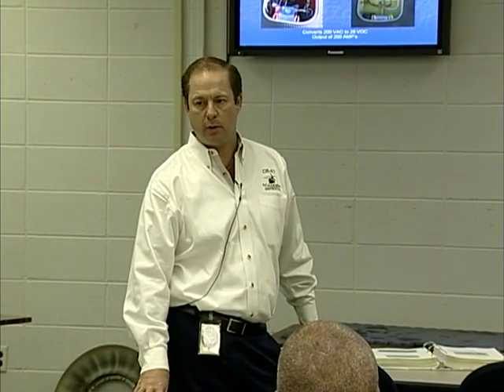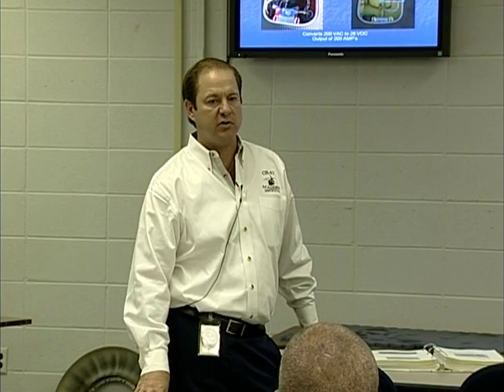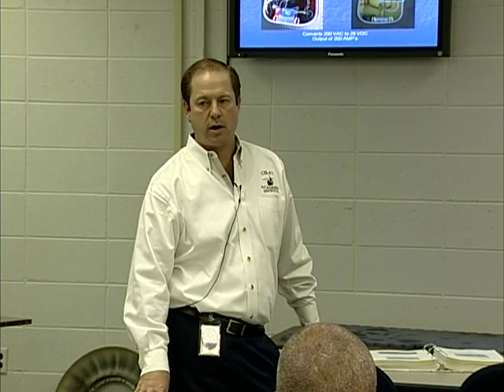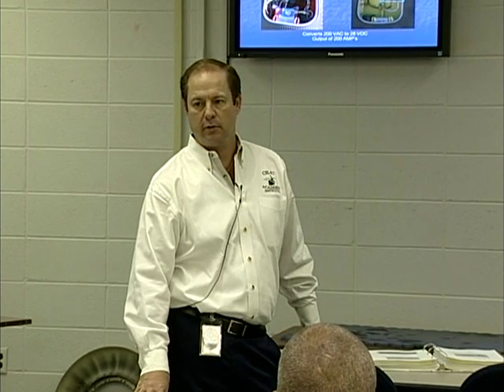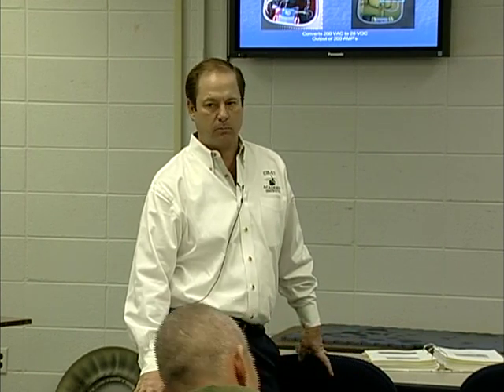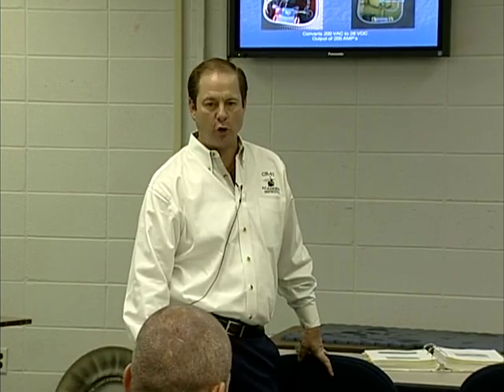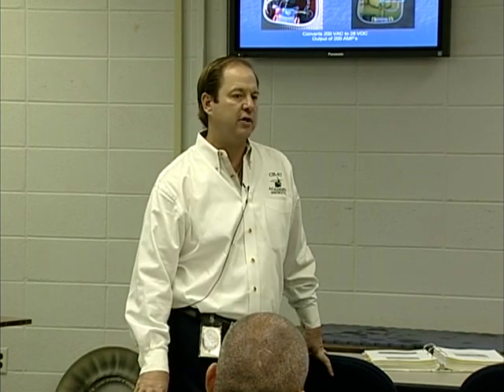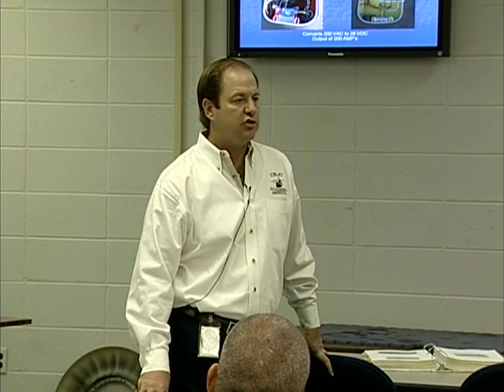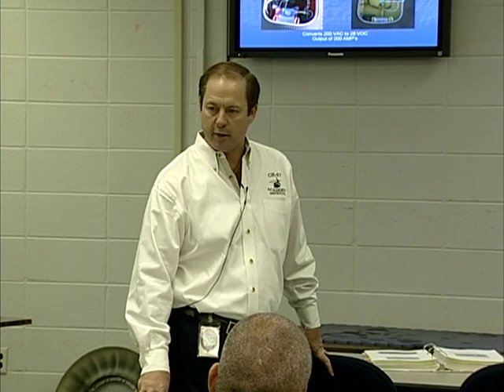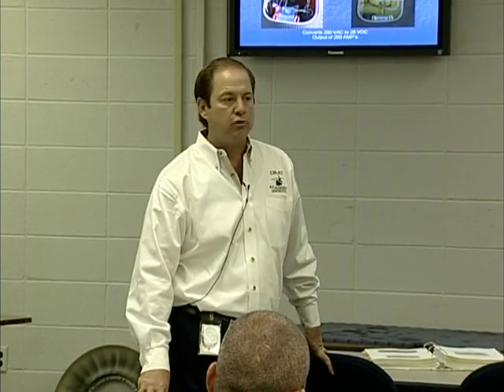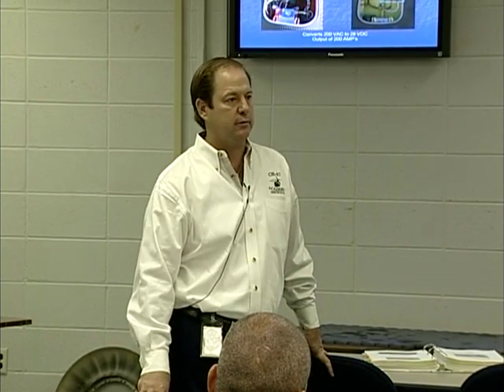Now those transformer rectifiers provide 200 amps. Why is that important to understand? How many amps does it take to kill a person? Less than 1. And you have 200 amps being created. We see people—since we've trained you so well to shake electrical connections to check for looseness—forget that if those transformer rectifiers are powered up, trying to check for looseness can get you killed.